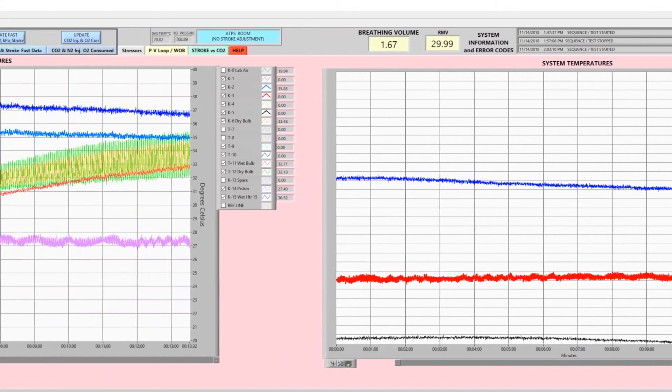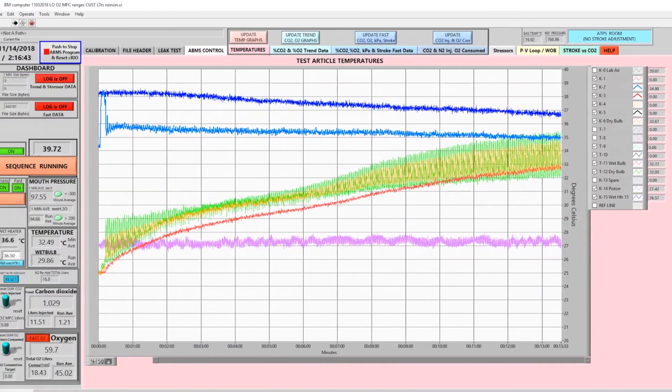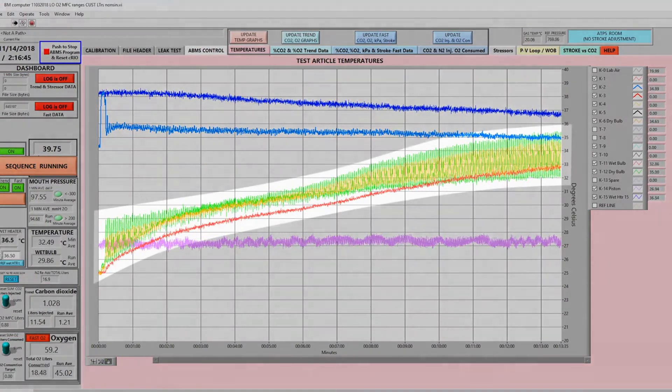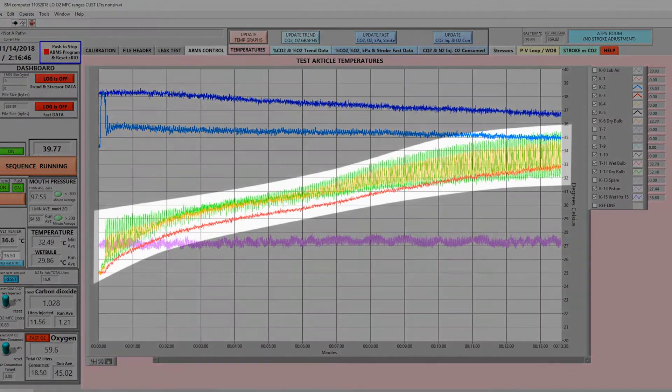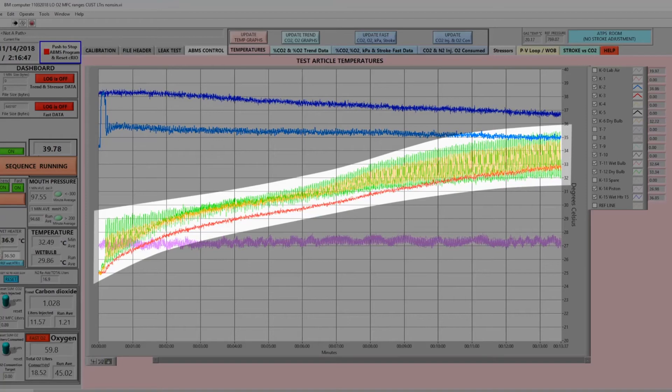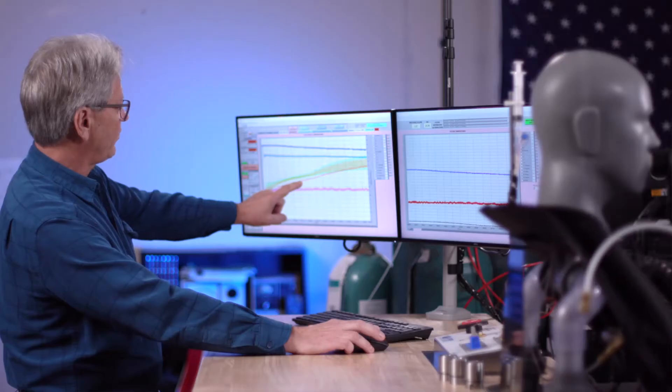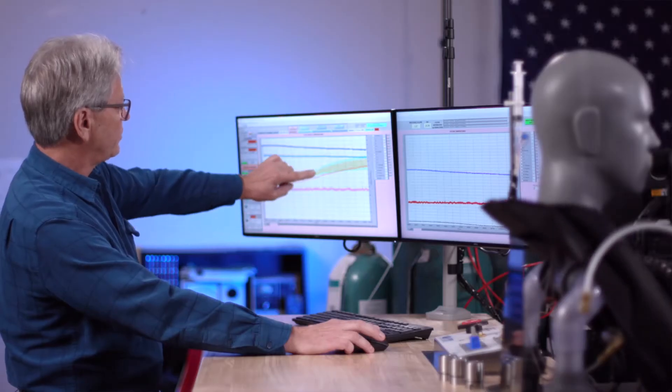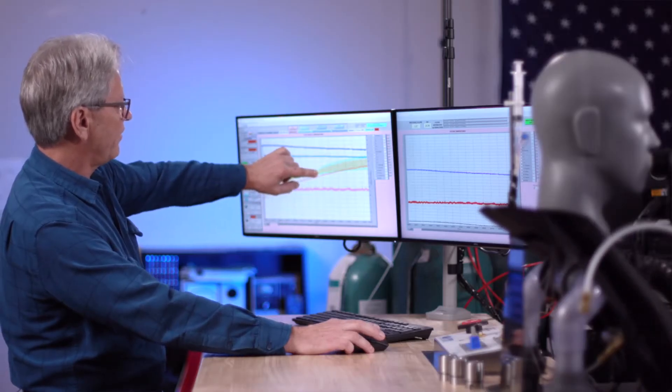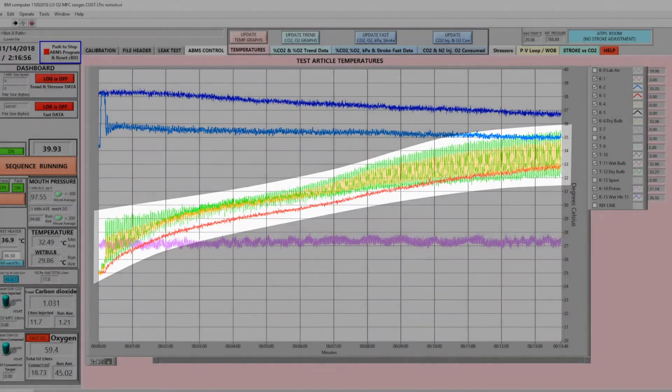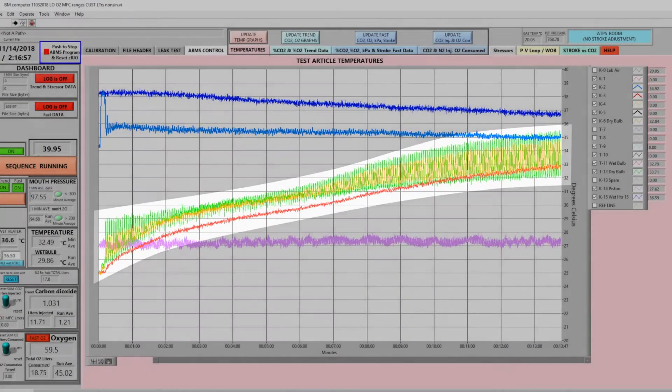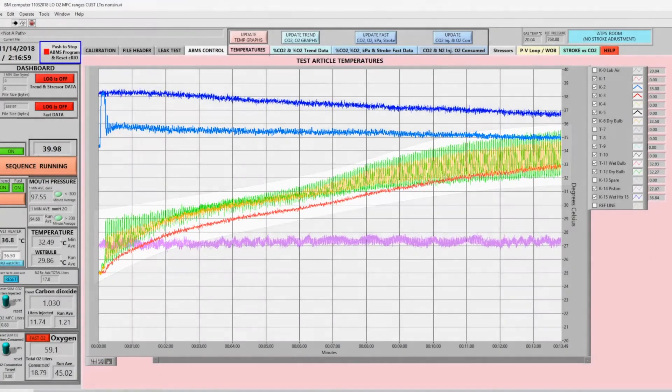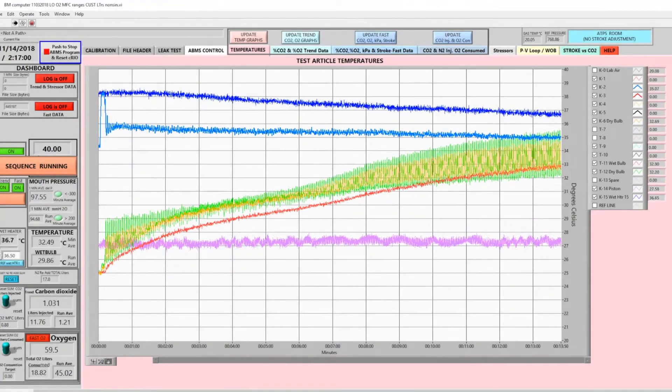On the left screen, we see the apparatus under test and the three probes in the mouth as we are breathing. Here the wet probe and two dry probes that are in there coincide very well to give a profile of the temperature changing as the system is breathing on the apparatus.